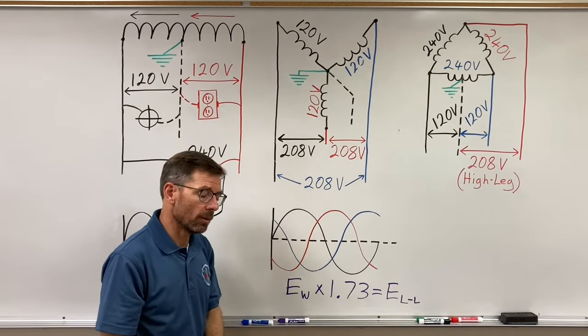One other note: the neutral point, labeled X0, is generally taken to ground in a transformer classified as a separately derived system. Because that same point is taken to ground, this neutral conductor is essentially taken to ground as well. Thereby, we call the neutral most of the time in the code the grounded conductor — not always, but most of the time.